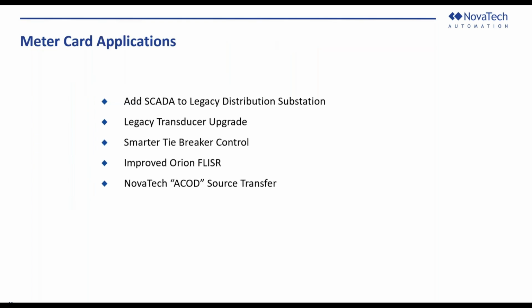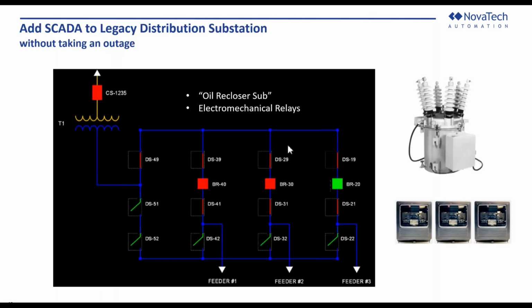So we talk about 5 applications. The first is adding automation, adding SCADA to legacy distribution substations that don't have any automation. We'll talk about an upgrade of older transducers, smarter tiebreaker control, a better FLISR solution. Actually, I should say an alternate lower cost FLISR solution, and this ACOD automatic changeover device solution for source transfer. This is a packaged system from our NovaTech systems operation. Start with this one here.